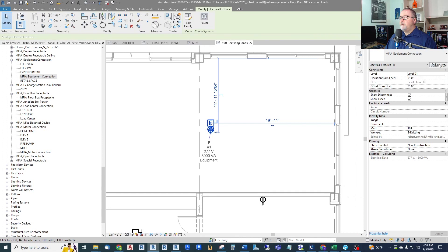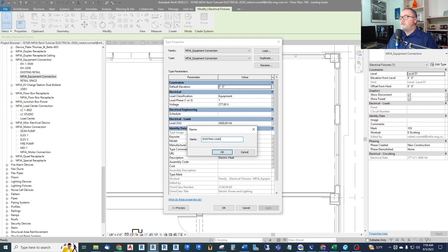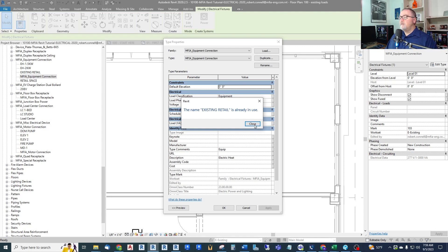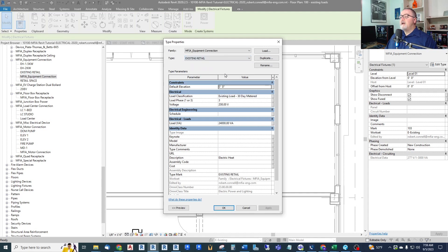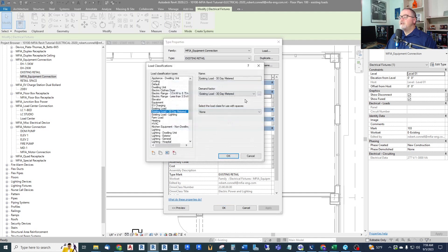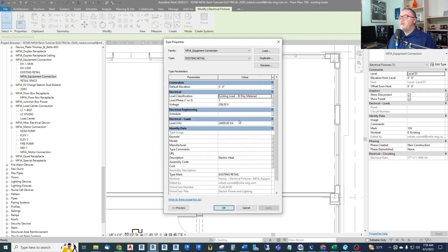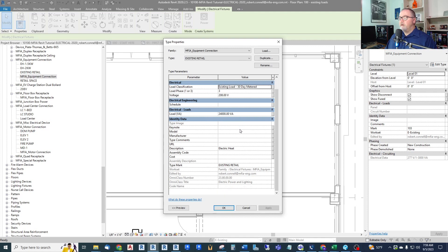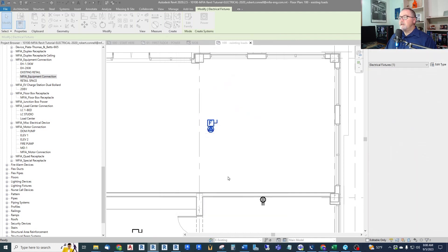I need to duplicate this and call it existing load. And if I had multiple existing loads, I might call this existing retail. Okay, looks like I'd already created one before. So we'll use that. And we can set the load classification to, there's a number of existing kinds of loads. We can go existing load 30-day metered. I'm going to call it existing 30-day metered. And this applies a demand factor of 125%, which we couldn't do with that spare process. And then I'll give it a load. I gave it 24 kVA load. And this is not needed. We're not going to have this in a schedule. And we're going to call this existing retail.